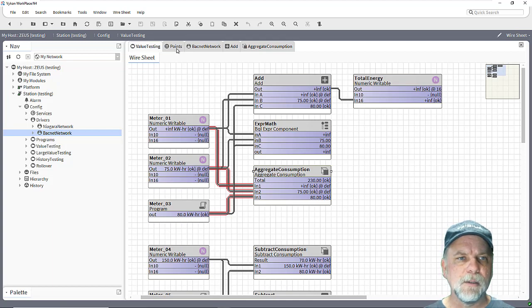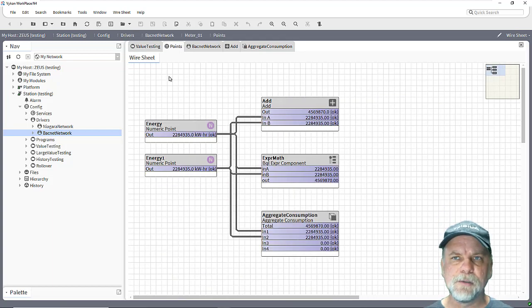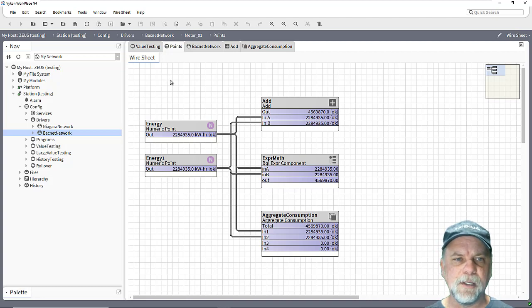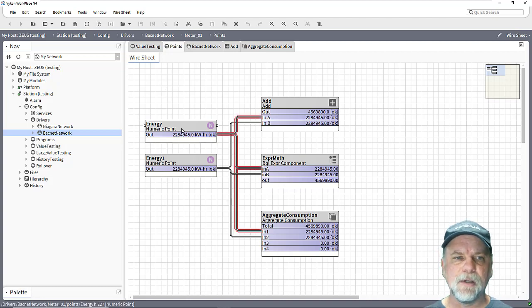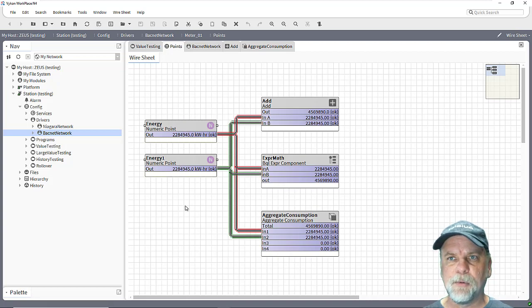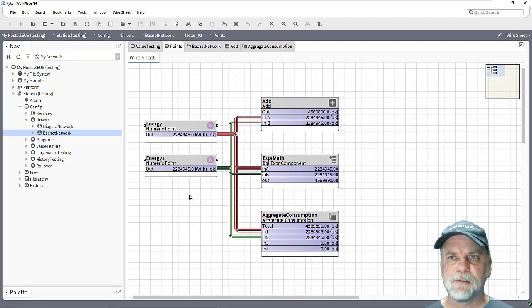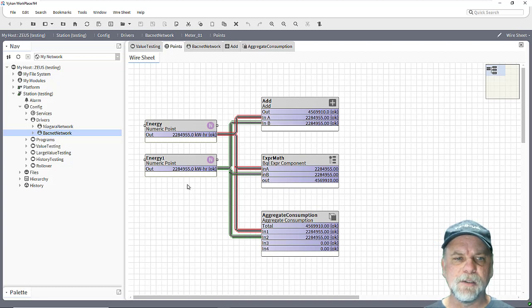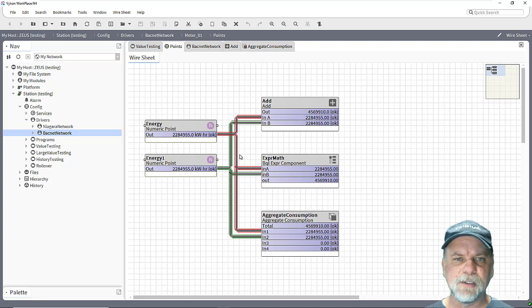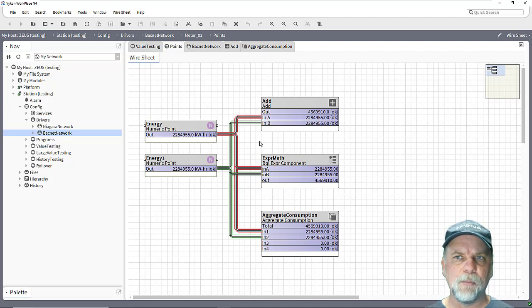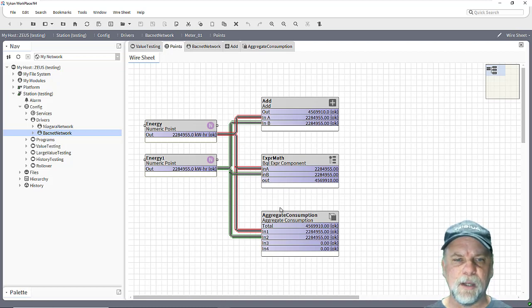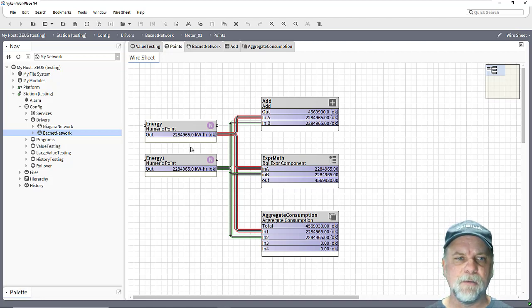All right, let's talk about some other scenarios on the data integrity and validity as well. In this case I have two BACnet proxy points here under a BACnet device, sort of simulating a smart meter, and these are totalized values that are increasing and same sort of scenario of them being linked into add blocks or expression math or aggregate consumption as far as these having invalid statuses or invalid values.